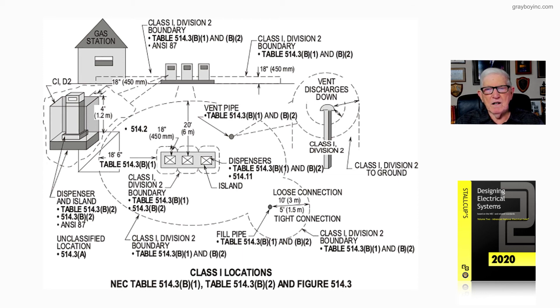So we have to look at that. Loose connection, 10 feet out. Nothing can go there without being rated for a Class 1 Division 2 location if you're in that area. 5 feet out would be for a tight connection. And all those boundaries are found in the table, as you see there, 514.3B1 and B2.